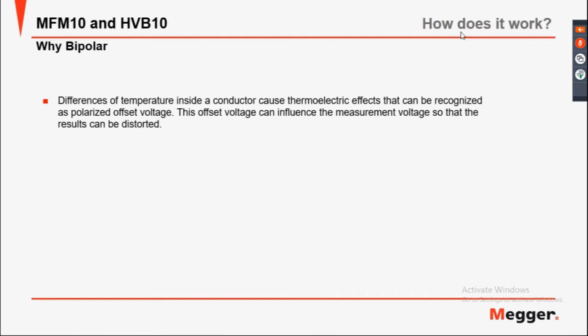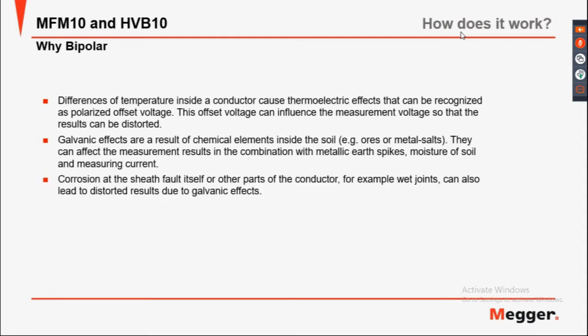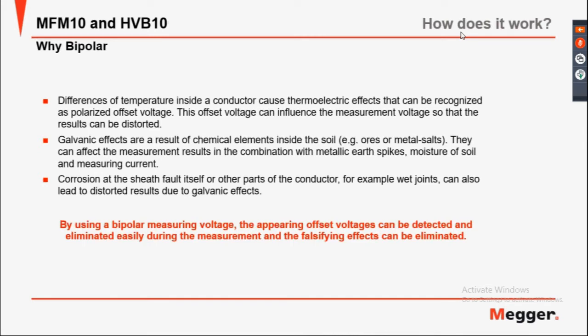Why do we apply bipolar measurement? Temperature differences inside a conductor cause thermoelectric effects that can be recognised as a polarised offset voltage. This offset voltage can influence the voltage measurement and distort the result. Galvanic effects result from chemical elements inside the soil — ores, metal salts — which can affect measurement results in combination with metallic earth spikes, moisture of soil, and measuring current. Corrosion at the sheath fault itself or wet joints can also lead to distorted results. By using bipolar measurement, these offset voltages can be detected and eliminated during measurement.